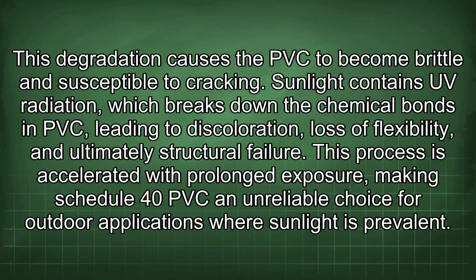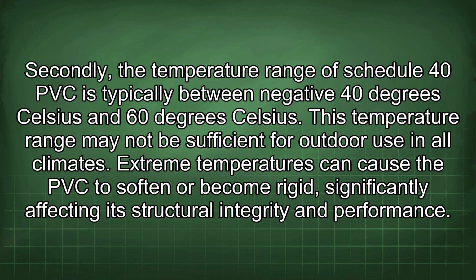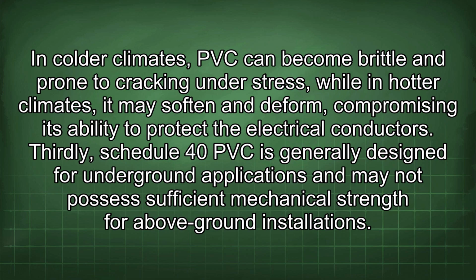sunlight is prevalent. Secondly, the temperature range of Schedule 40 PVC is typically between -40°C and 60°C. This temperature range may not be sufficient for outdoor use in all climates. Extreme temperatures can cause the PVC to soften or become rigid, significantly affecting its structural integrity and performance. In colder climates, PVC can become brittle and prone to cracking under stress, while in hotter climates, it may soften and deform, compromising its ability to protect the electrical conductors.